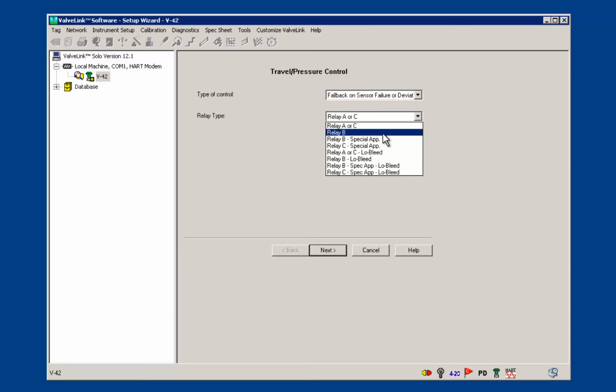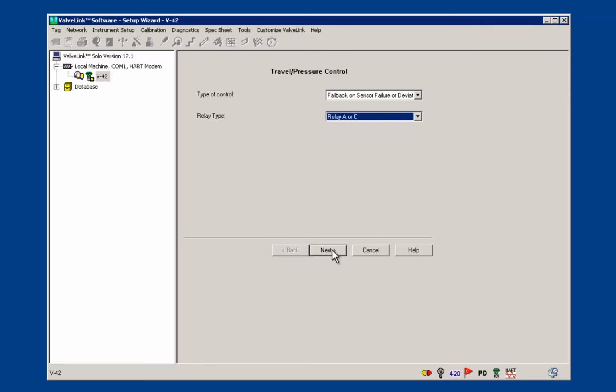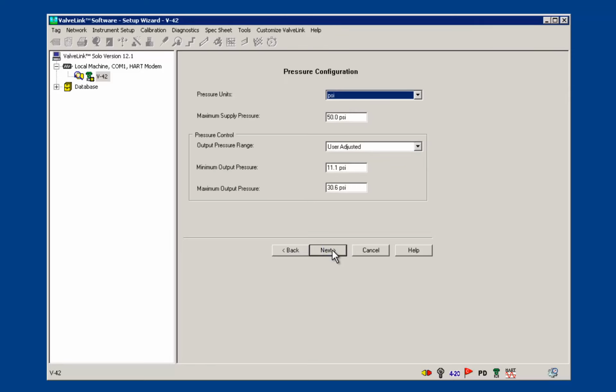If you have an SIS unit, a low bleed option, or are unsure, check the relay type by removing the instrument cover and finding the label on the relay. Select your relay type from the menu and click Next. Now choose the pressure configuration settings. First, choose your pressure units. The default is bar, but I'm going to select PSI.